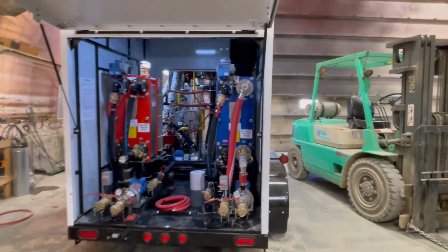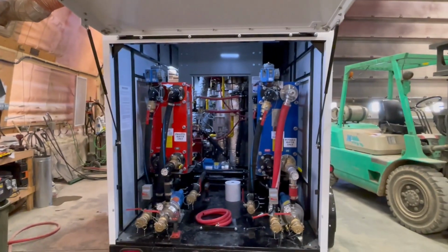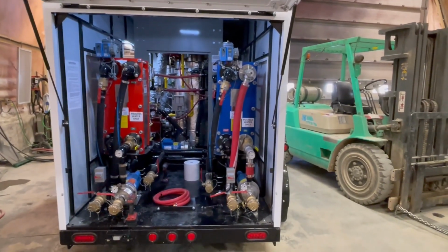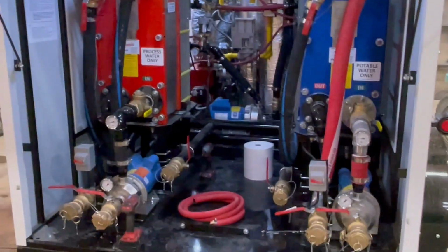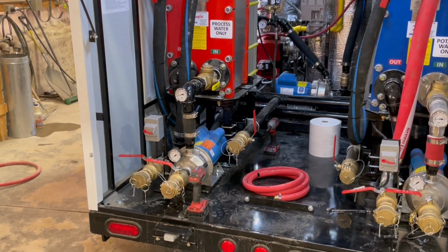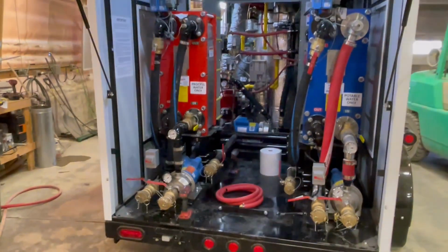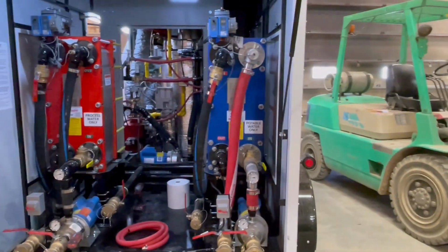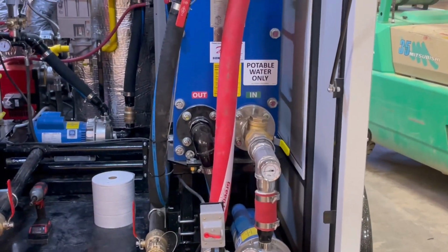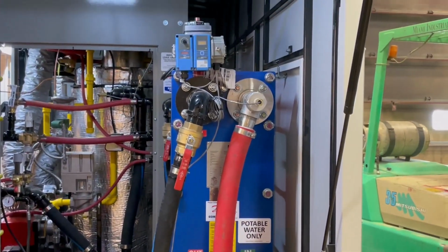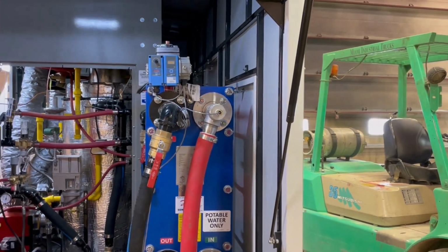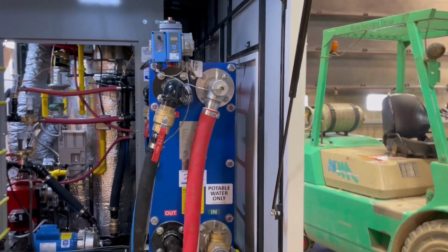On the rear of the unit are two plate heat exchangers. The red is a processed water and the blue is potable water. Each has a 3 horsepower pump operating on the water side of the plate heat exchanger. On the plate, the bottom left plumbing is the glycol outlet, and the plumbing above is the glycol inlet. On the right side, the top is the water outlet, and the bottom is the water inlet, plumbed into the water circulation pump.